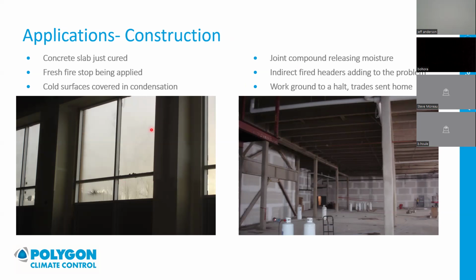You can see these windows covered in condensation, because that air, when it touches the window, gets colder, shrinks, and can't hold all the water it has since it's already saturated, so that water sticks to the window. So the solution was: let's heat up the building, it's wet, if we heat it we can dry it out and get the moisture out. You can see all these propane bottles scattered around, and on this one you can actually see flame on the end. This is a good example of the most simplified direct-fired heating system you can imagine: a bottle of gas with a regulator and a flame on it.